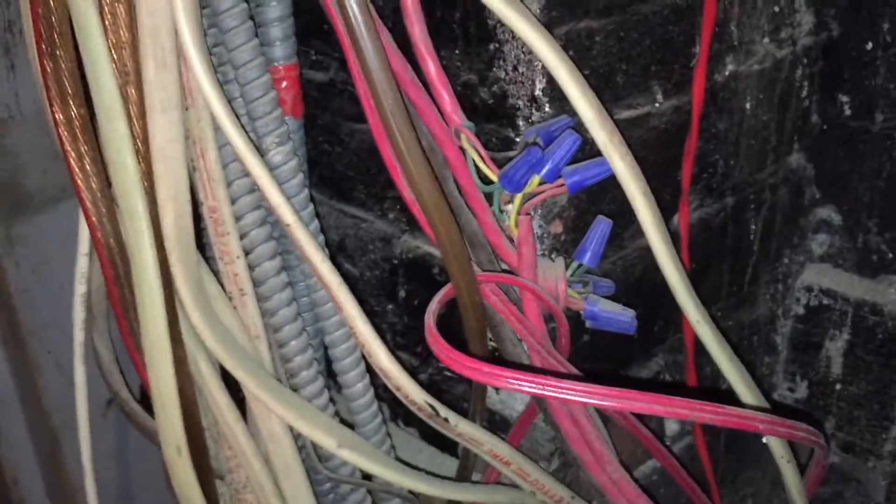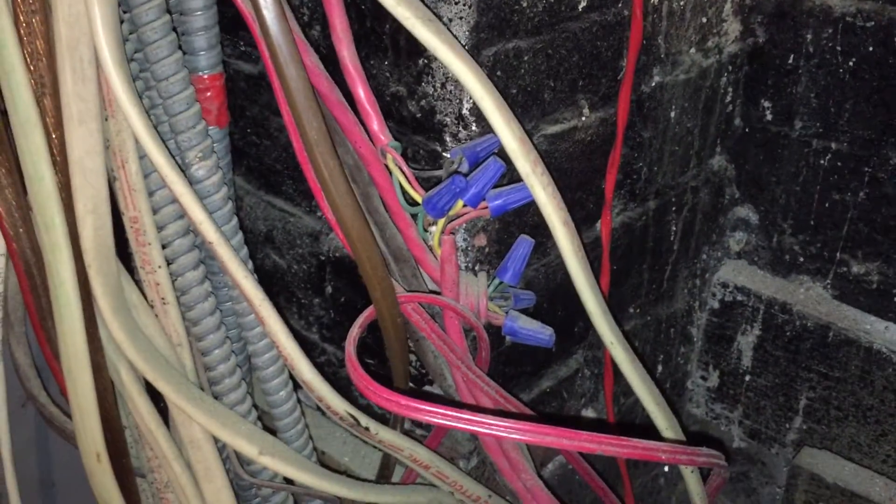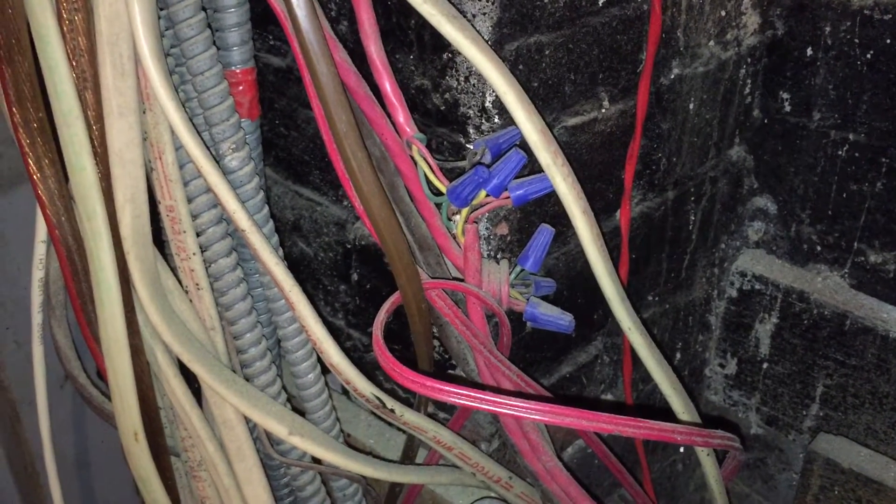These splices need to be protected, and also these cables are not properly supported by any stretch of the imagination. We'll talk about those in another video. This is Russell Blank, NEC consultant for EC&M magazine.